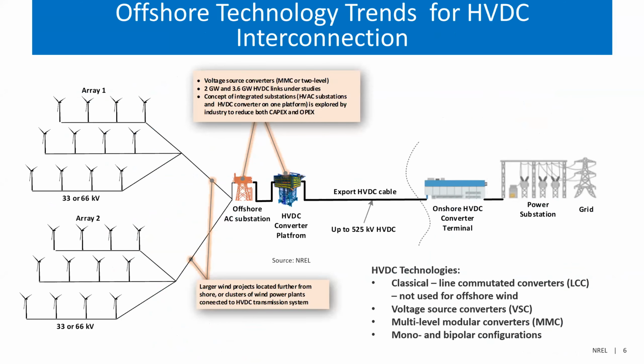For high voltage DC transmission it is the same. The 66 kilovolt AC collector system can be utilized, and the main driving factor for cost reduction is the HVDC converter platform design, combining the AC substation and HVDC converter platform in one structure and making it as self-erecting as possible, and using higher voltage export cables. The main converter technologies used for offshore wind power are voltage source converters, and lately multi-level modular converter, MMC, technology is starting to be introduced into the market. Configurations for this HVDC transmission can be both monopole or bipolar. Bipolar has a higher reliability, of course.